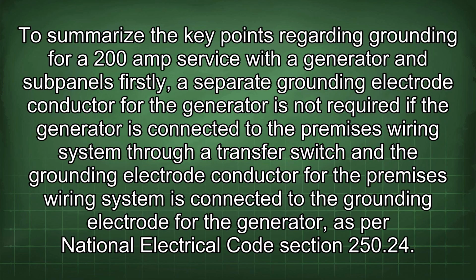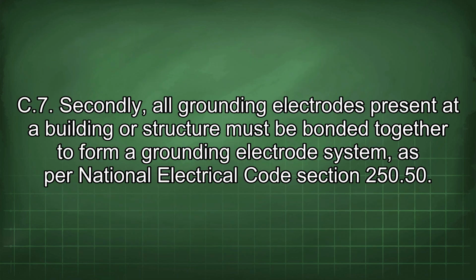To summarize the key points regarding grounding for a 200 amp service with a generator and subpanels: firstly, a separate grounding electrode conductor for the generator is not required if the generator is connected to the premises wiring system through a transfer switch and the grounding electrode conductor for the premises wiring system is connected to the grounding electrode for the generator, as per National Electrical Code Section 250.24(C)(7). Secondly, all grounding electrodes present at a building or structure must be bonded together to form a grounding electrode system, as per National Electrical Code Section 250.50.